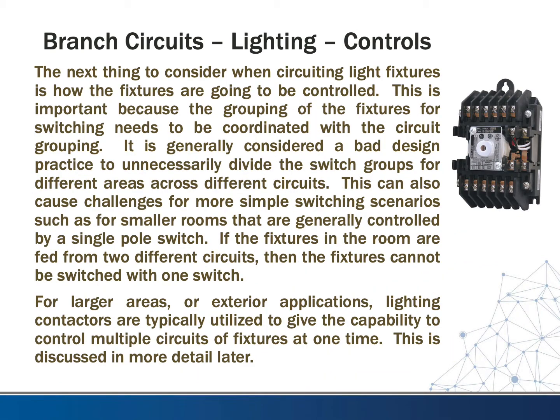The next consideration when circuiting light fixtures is how the fixtures will be controlled. The grouping of fixtures for switching must be coordinated with the circuit grouping. It is generally bad design practice to divide switch groups for different areas across different circuits, which can cause challenges for simple switching scenarios — if fixtures in a room are fed from two different circuits, they cannot be switched with a single switch. For larger areas or exterior applications, lighting contactors are typically utilized to control multiple circuits at once. A lighting contactor can run up to six circuits and can be controlled by a single-pole switch, an electrical impulse, or a signal from a building automation system.